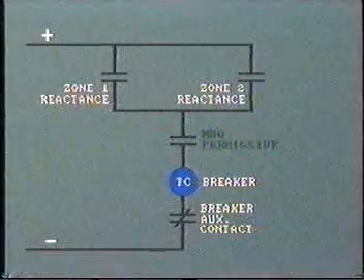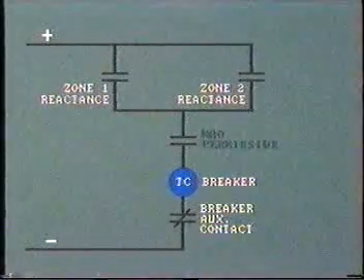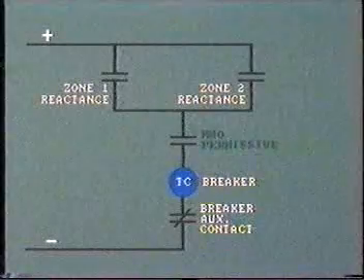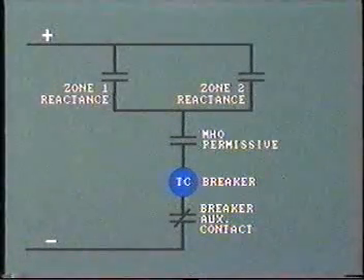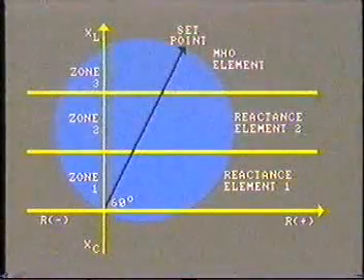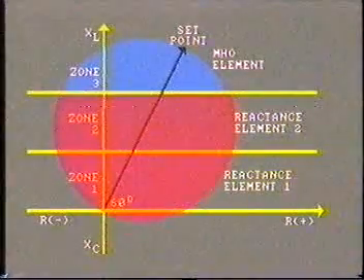But additionally, the Mho element also contains a permissive contact in the operating circuit of the reactance relays. This restricts operation of the reactance relays to this area.